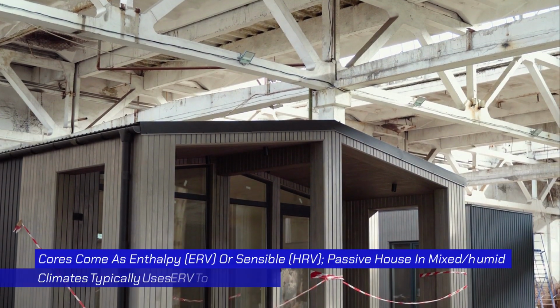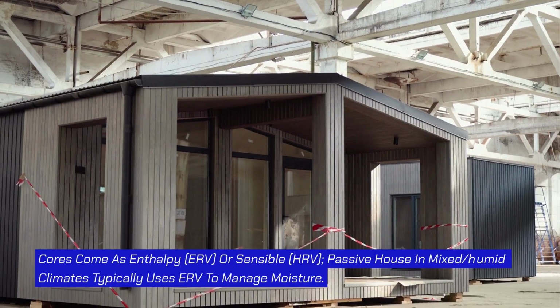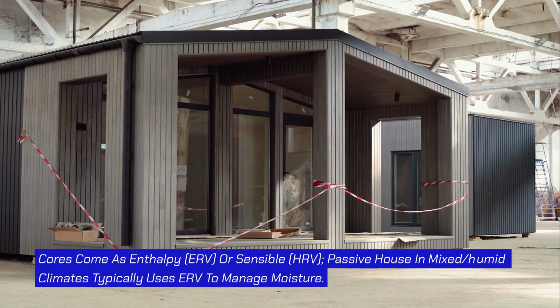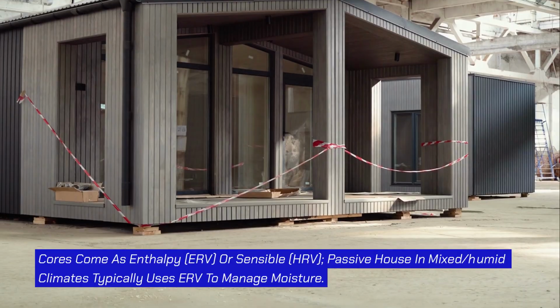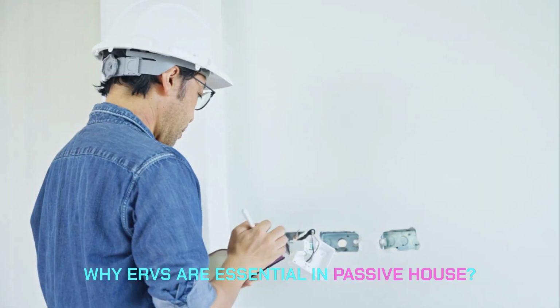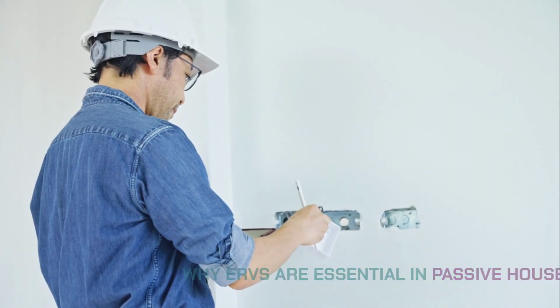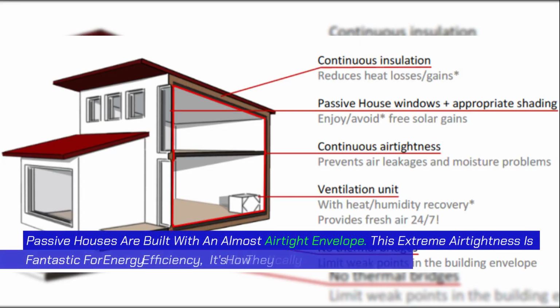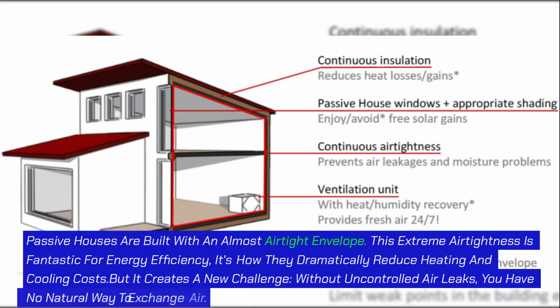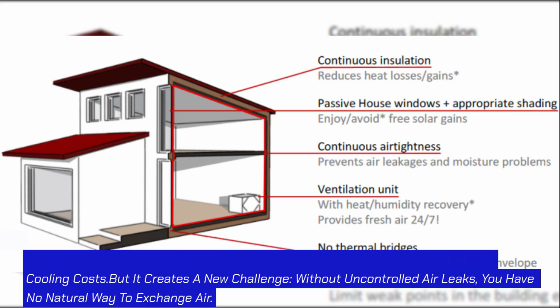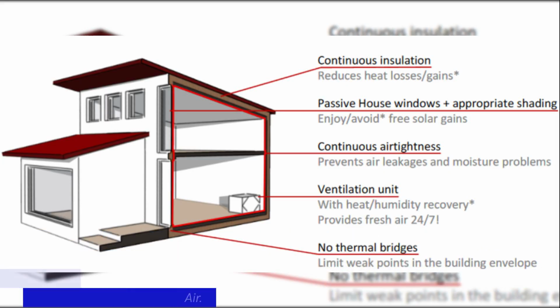Cores come as enthalpy, ERV, or sensible, HRV. Passive house in mixed, humid climates typically uses ERV to manage moisture. Why are ERVs essential in passive house? Passive houses are built with an almost airtight envelope. This extreme airtightness is fantastic for energy efficiency. It's how they dramatically reduce heating and cooling costs. But it creates a new challenge. Without uncontrolled air leaks, you have no natural way to exchange air.